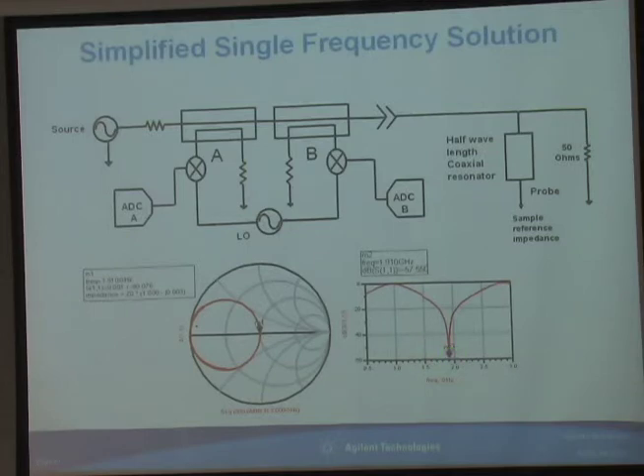At roughly 1.9 gigahertz, you have this state where you have very sensitive measurement. This will recur every time you repeat a half wavelength, so you have 2, 4, 6, 8, 10, 12, 14 - you can actually measure up to 20 gigahertz with this instrument. This is the way we do our imaging with the microscope: we run the network analyzer through this null and look at the null shift as a function of impedance perturbation on the surface of the sample. That allows you to convert it into an image.